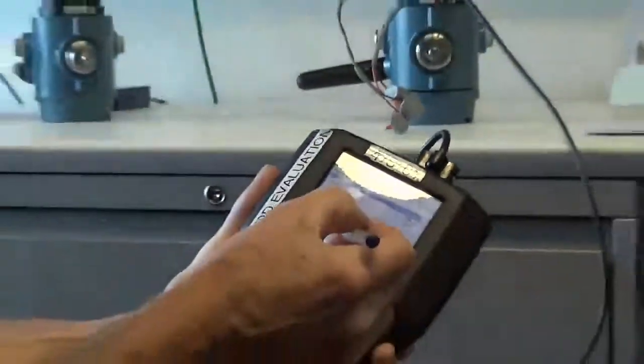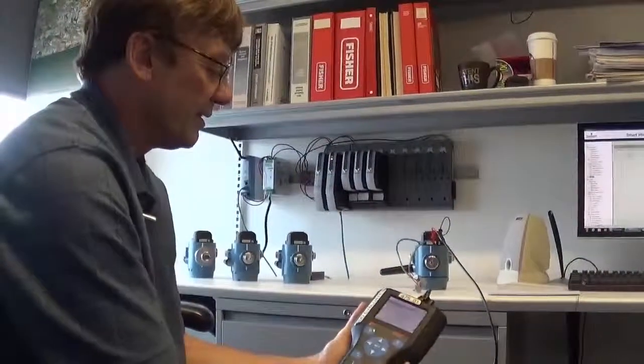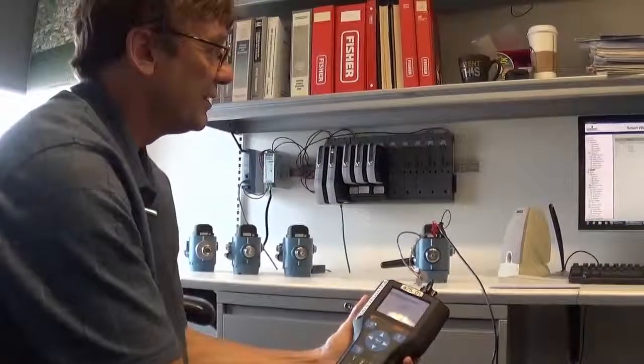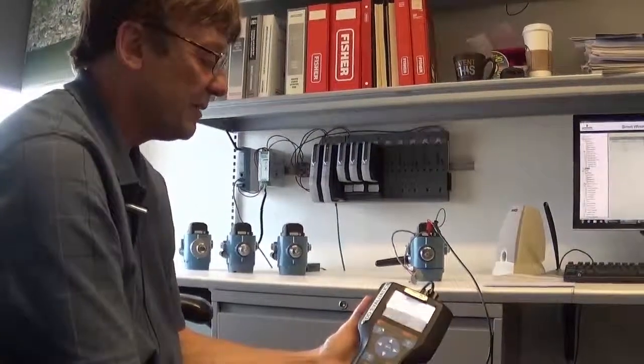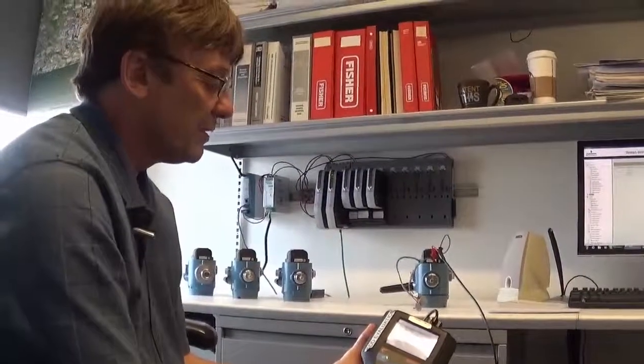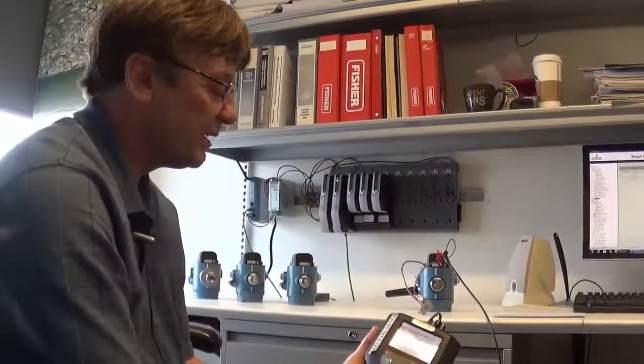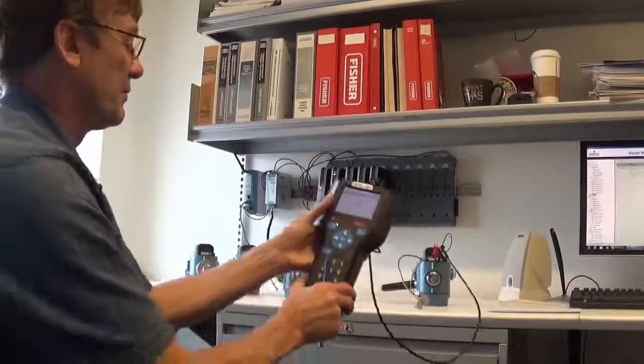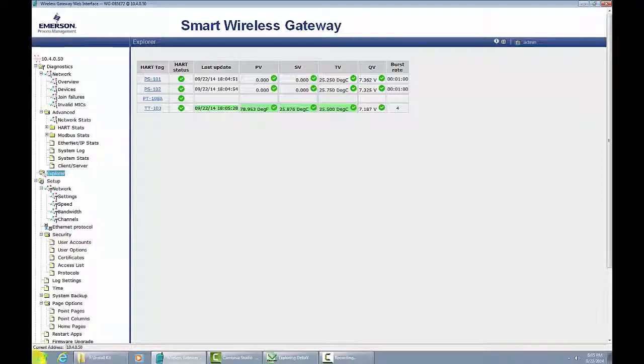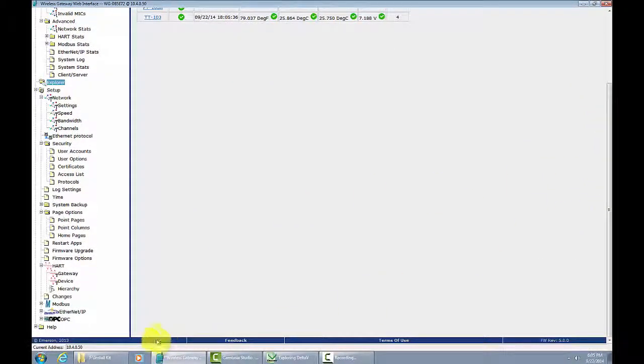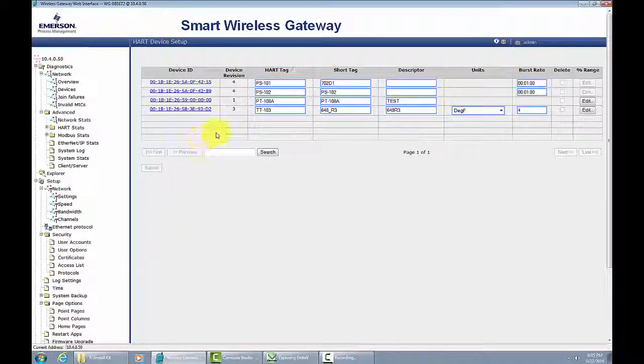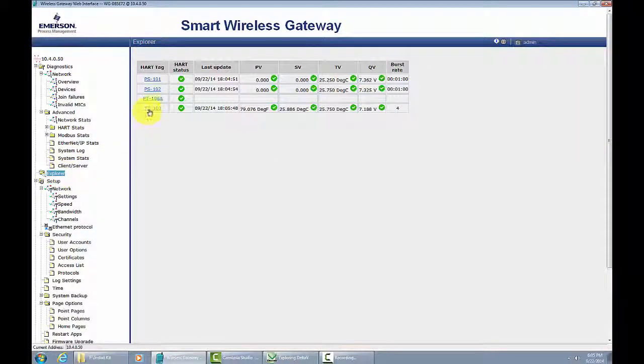So we'll just save that. And so this device should be ready to communicate now on the network. So at this point, we'll switch back to the Wireless Gateway Explorer and take a look at the device, which should begin to show up momentarily on the network. At this point, we're looking at the Wireless HART Gateway. The device has shown up, it's joined the network and shown up as TT103. We can also look at the device in the hierarchy as a device, and we can see the tag and the device ID. And going back, we can again see it on the Wireless HART Explorer.